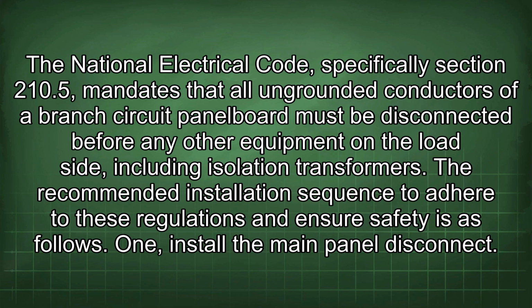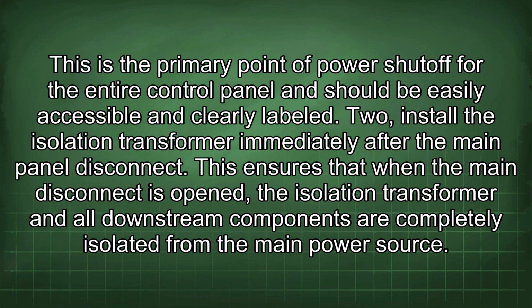1. Install the main panel disconnect. This is the primary point of power shutoff for the entire control panel and should be easily accessible and clearly labeled. 2. Install the isolation transformer immediately after the main panel disconnect. This ensures that when the main disconnect is opened, the isolation transformer and all downstream components are completely isolated from the main power source.